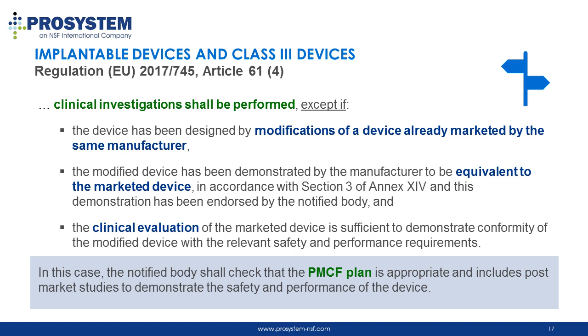You should also make sure that a clinical investigation is not mandatory for your device. For class 3 devices, clinical investigations should always be performed, except if the device has been designed by modifications of a device already marketed by the same manufacturer, the modified device has been demonstrated by the manufacturer to be equivalent to a marketed device, and the clinical evaluation of the marketed device is sufficient to demonstrate conformity of the modified device with the relevant safety and performance requirements.